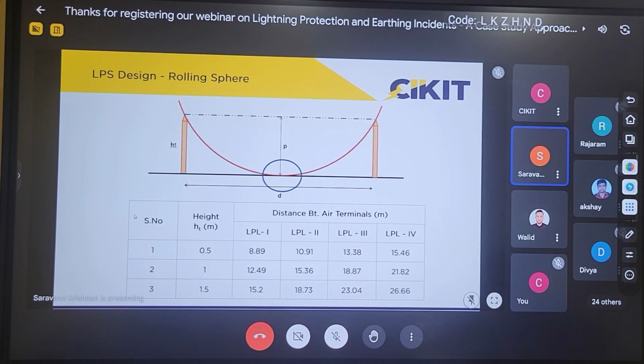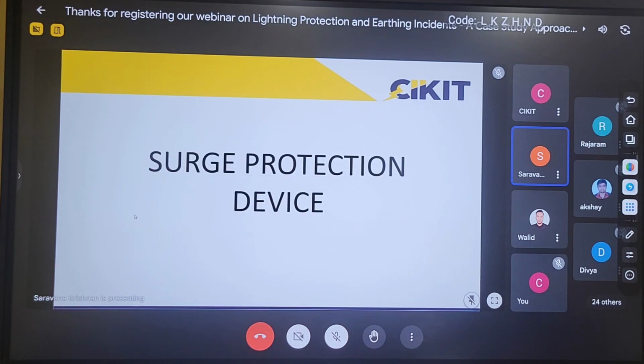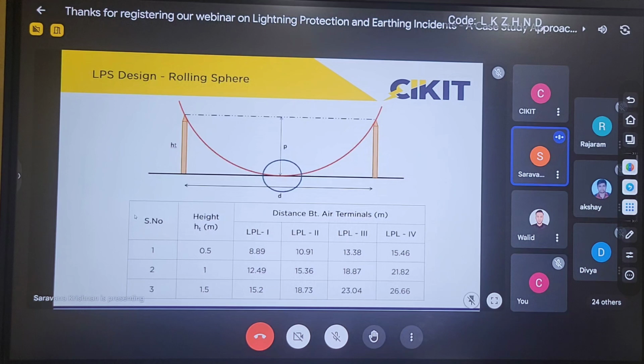So the next important topic is surge protection devices. From these slides, we can observe that if I am going for a vertical air termination system, then these two methodologies, the protection angle method and the rolling sphere method, can be used. It is not mandatory that I go only for the protection angle method or only for the rolling sphere method. Based upon the site conditions, we can determine which method will be suitable.